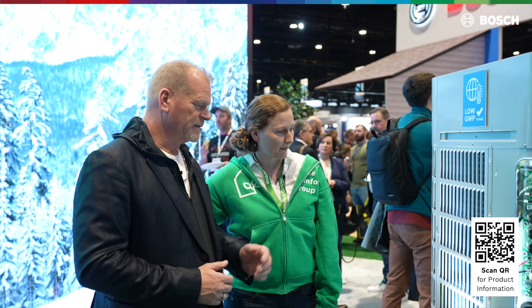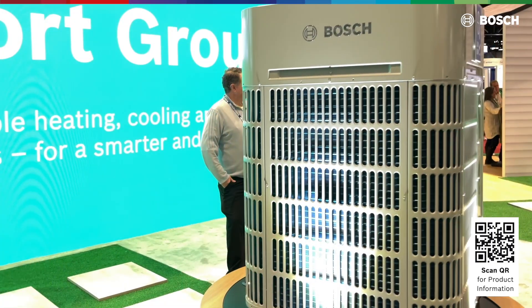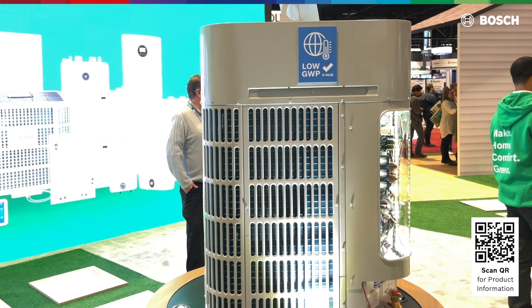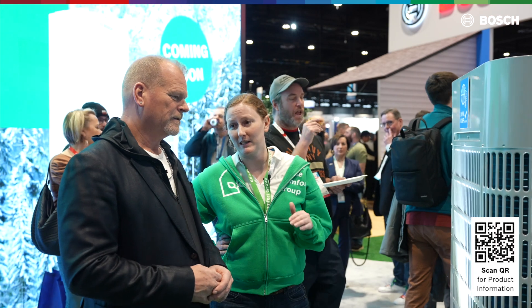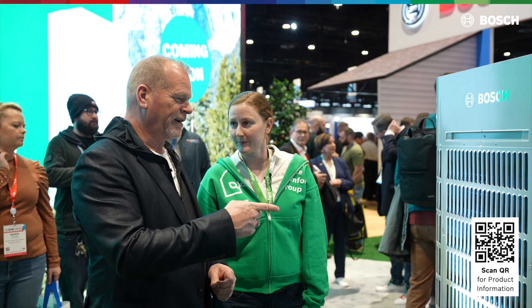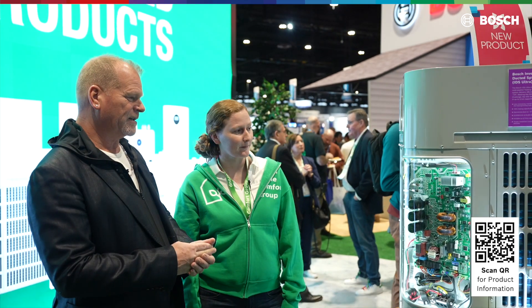Regardless of the application, the heat pump will send heat where it needs to go — outside when it's hot, inside when it's cold. This unit is a four ton, so around 48,000 BTU, and it'll run at 100% capacity down to five degrees, whereas most equipment today only goes about 70% capacity at five degrees. That ability to maintain high capacity when it gets really cold is something this equipment is great at.